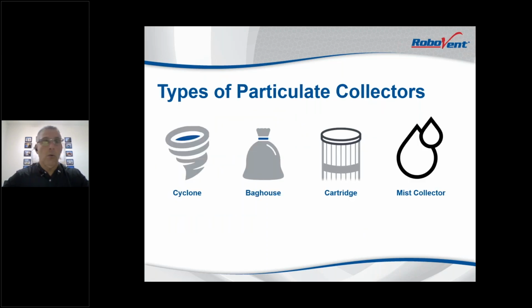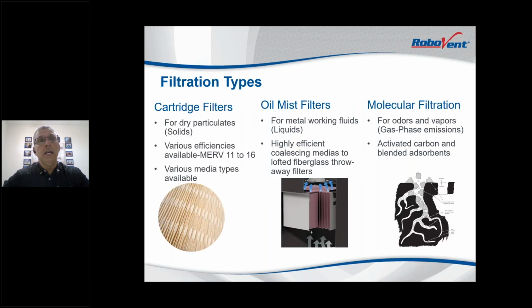So types of particulates, we'll wrap up here fairly quickly. Types of particulate collectors, and the heart, or really the base of the collector, is what type of filter you're using. If it's a dry process or MQL, you may want to go to a cartridge style filter that's meant for dry filtration. If it's a wet process, a filter that's meant for liquids, and there's a wide variety of those types of filters. There's filters that are near HEPA quality, 99% plus for submicron particles, and they tend to last a very long time if you deal with the non-solubles ahead of it. And then to the other extreme are lofted fiberglass throwaway filters that tend to last a few weeks, maybe a few months. So there's this extreme in efficiency and also longevity of the filters.